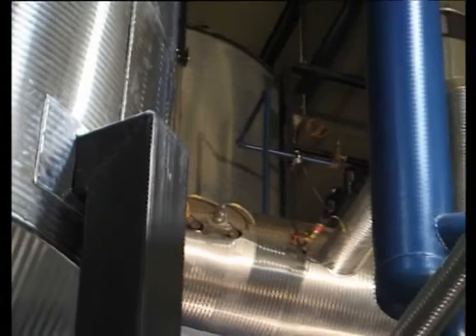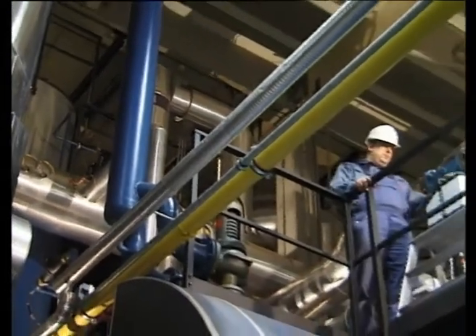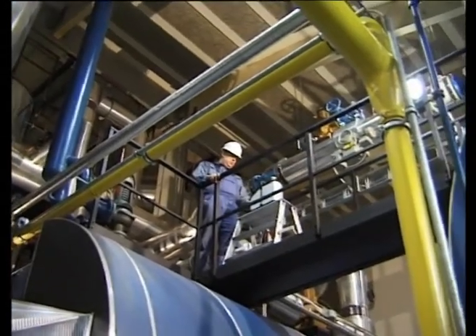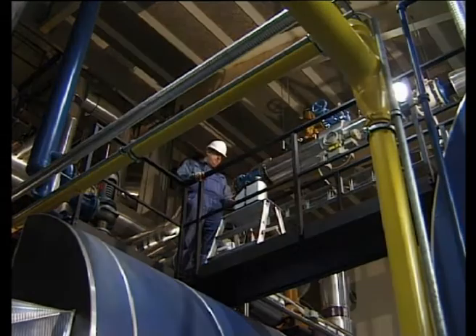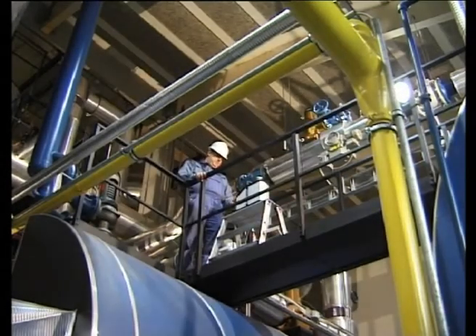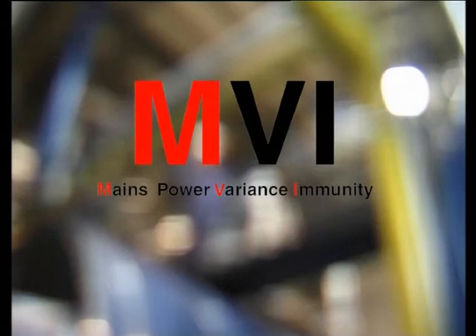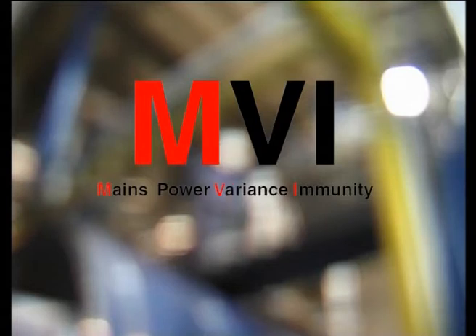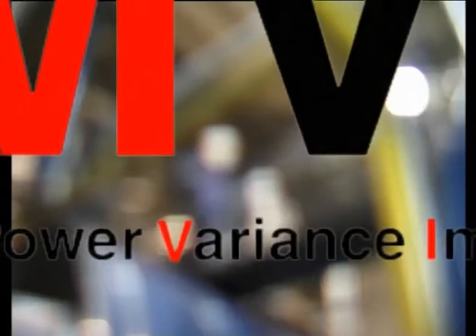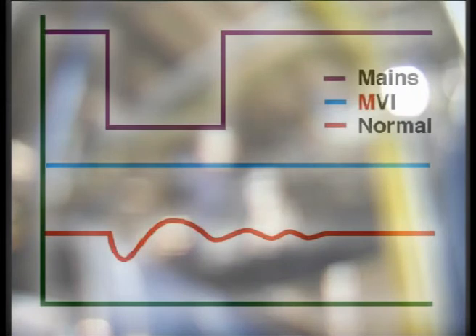Amatec has identified a great risk for inaccuracy in on-site calibrations: an unstable main supply. Large electric motors, heating elements, and the like switch on and off in the production environment. This means that the temperature regulator in traditional temperature calibrators becomes unstable. Sometimes this may result in as much as several degrees deviation. To provide you with 100% confidence in the ATC series, Amatec has developed MVI, Main Power Variance Immunity, a unique innovation for temperature control in calibration equipment. MVI eliminates the problem, because variations in the incoming voltage are registered immediately, and the MVI circuitry keeps the energy flow constant. The result is a problem-free calibration where you can trust the stability.